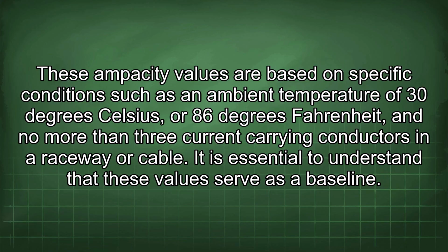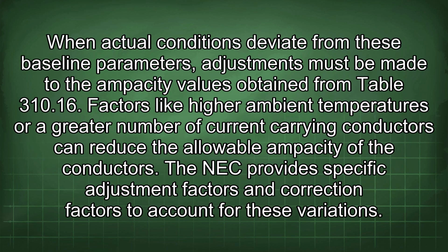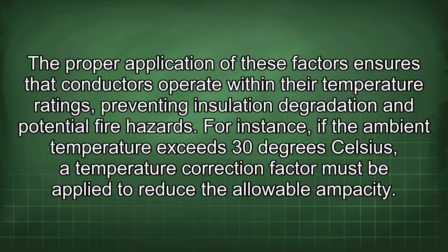It is essential to understand that these values serve as a baseline. When actual conditions deviate from these baseline parameters, adjustments must be made to the ampacity values obtained from Table 310.16. Factors like higher ambient temperatures or a greater number of current carrying conductors can reduce the allowable ampacity of the conductors. The NEC provides specific adjustment factors and correction factors to account for these variations.